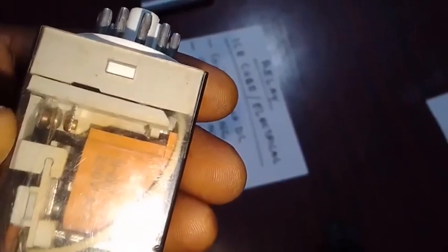When the field is set, a force is created between these two coils. If you check, there is a normally closed contact existing when the coil is not yet energized. But as soon as it's energized and a field is created, the magnetic field is capable of pulling this common contact towards the normally open contact, making it close.